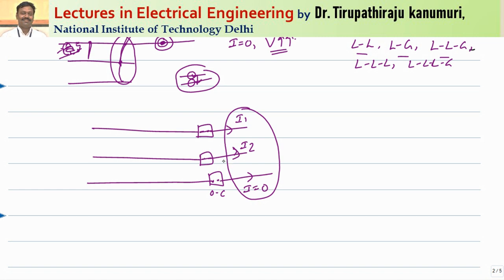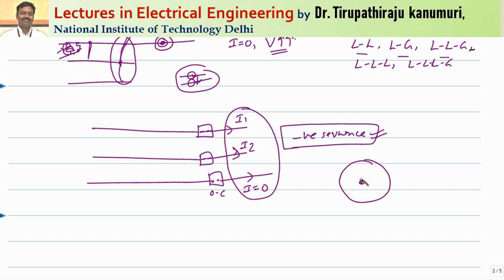The unbalanced system can be represented as a sum of positive, negative, and zero sequence components. The negative sequence components will start passing. In a motor or generator, if positive sequence components rotate in one direction at speed Ns, the negative sequence components will rotate in the opposite direction at speed Ns. The relative speed between positive and negative sequence components will be two times Ns. The EMF induced in the rotor is proportional to this relative speed, so huge voltages are produced.